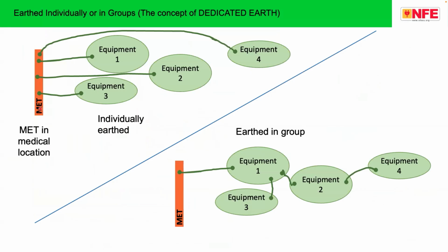Now, sometimes biomedical equipment require individual earth. Sometimes the manufacturer says this as dedicated earth. Now, in the picture at the top, this is dedicated earth, means you have an operation theater, you have to have a common bus bar. Each of the equipment must be connected with a dedicated wire. Separate connections are required, and this is called individually earthed. Now, on the bottom, you can see earthed in group.